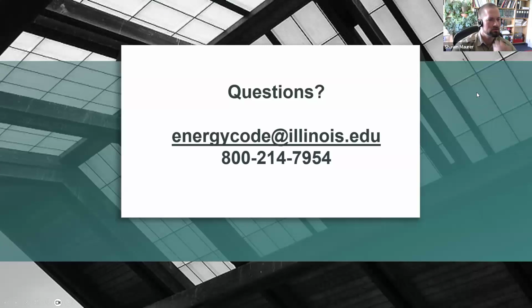All right, I think we'll do a couple of the quick ones that came in back with insulation. The first one was: is R5 insulation under the entire building slab for heated slabs, or is it some number of feet from the perimeter? For a heated slab, it's under the entire area of the heated slab. So if you have a portion of the slab that isn't heated, the R5 would go under the heated portion, and then you'd have to have that thermal break between the heated slab and the unheated portions of the slab.